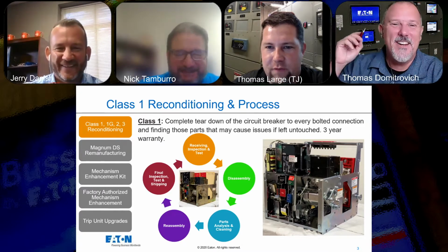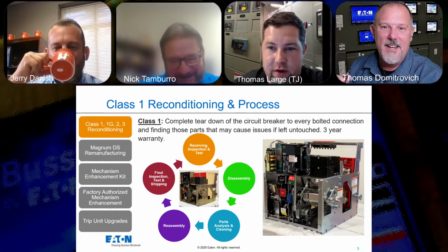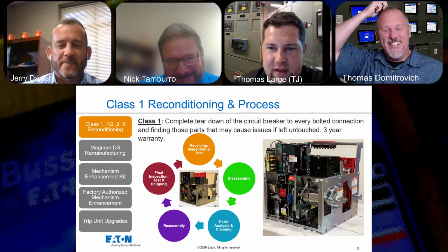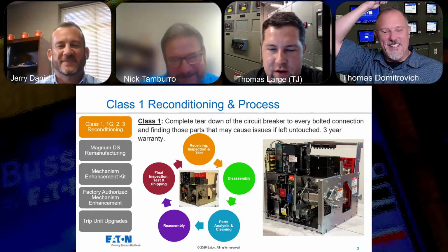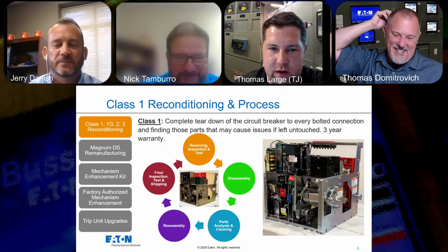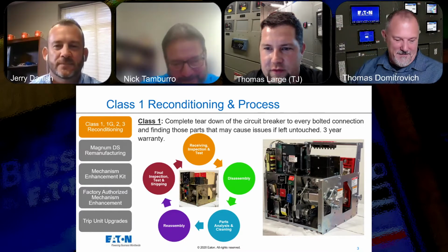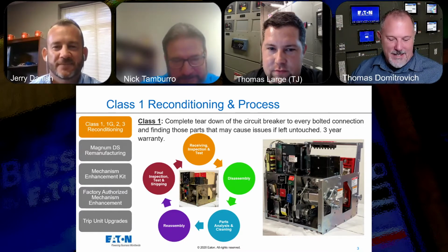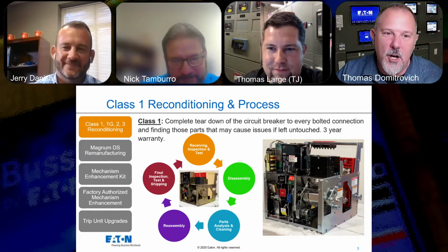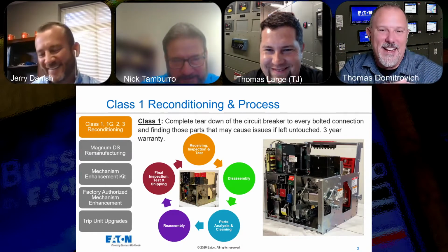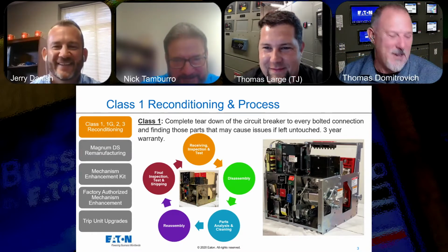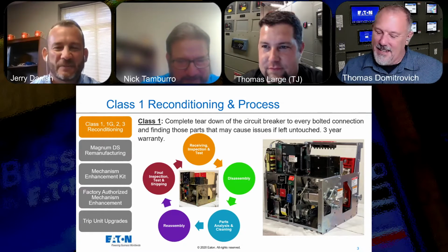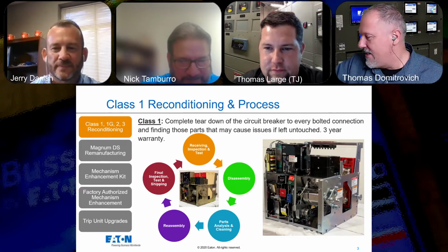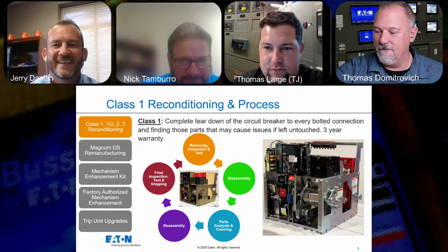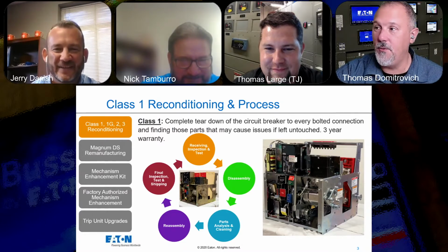We offer the low voltage vacuum replacement breaker. It replaces the mechanical copper components of your traditional breaker with vacuum bottles, which gives it a more robust operation life cycle. All you had to do was say snubbers, and I know because whenever you get into those vacuums, we start talking about the snubber actions.